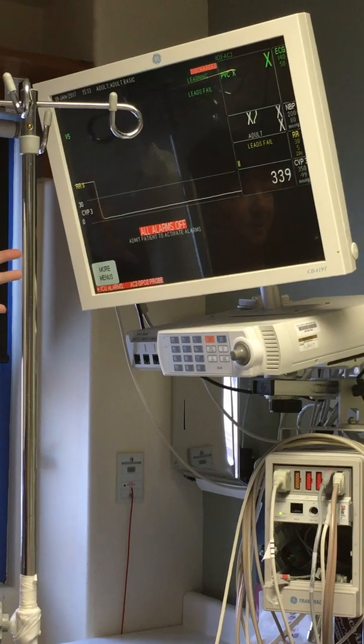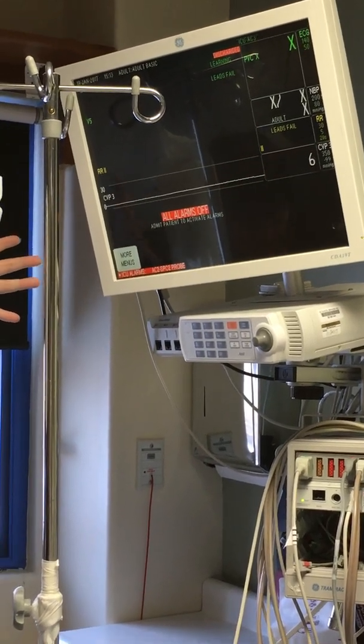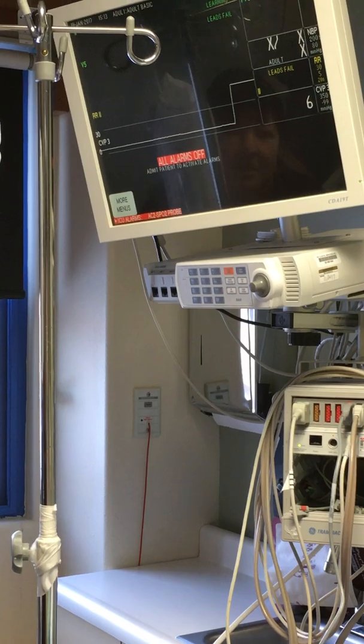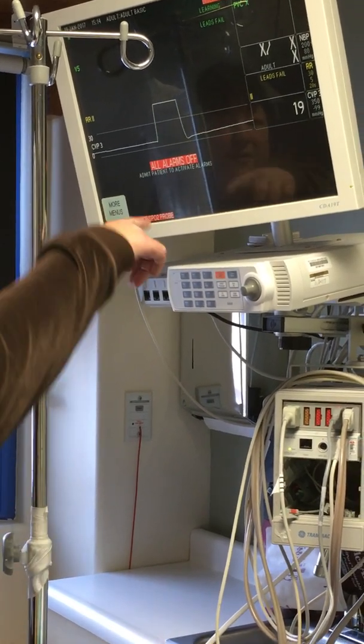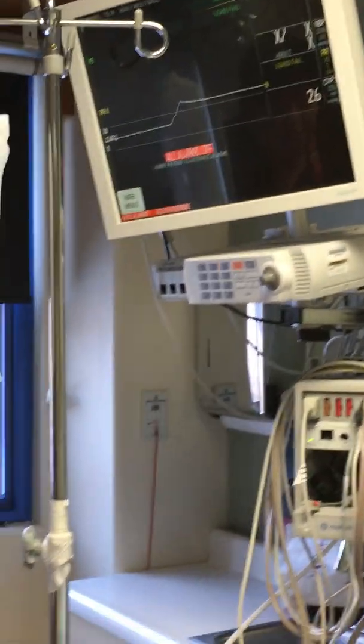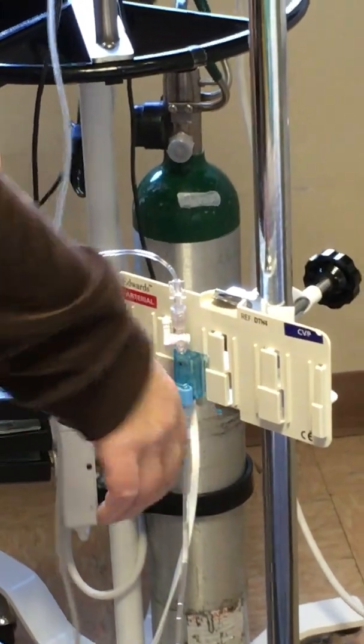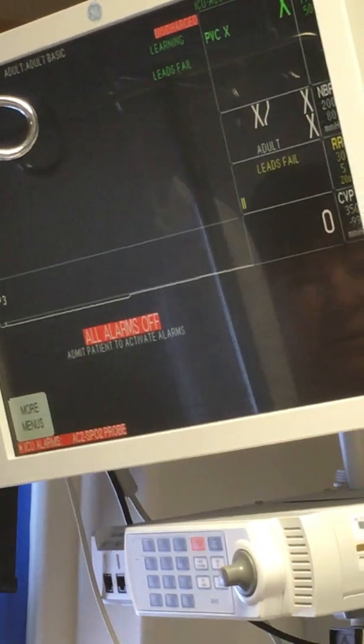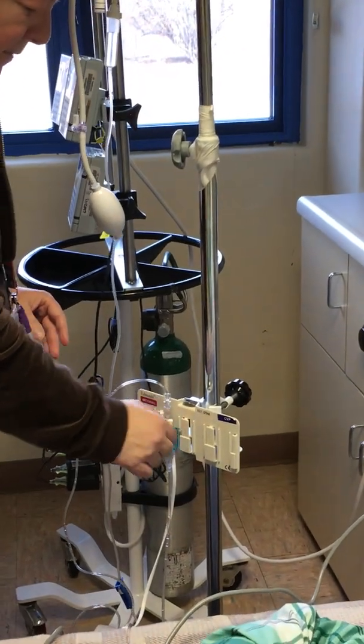Now that's not a very good square window because we're not transducing a real patient. What you can do is give it a flush. See, you want to look for a nice zigzag waveform after your square window. And then when you start transducing, you'll get a waveform and you'll get a CVP reading. So once again, same way every time. Off to the patient, open to air, flush, zero all, wait for your zero, make sure your hanging drip is right there, put your cap back on, and off to the port. Thank you.